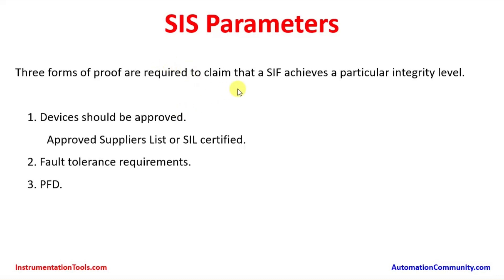Three forms of proof are required to claim that a SIF achieves a particular integrity level. First, devices should be approved — from an approved suppliers list or SIL-certified. Instruments and valves used in the safety instrumented system must come from approved suppliers and manufacturers, certified by agencies such as EXIDA or TÜV, which certify sensors, logic solvers, and final control elements against standards such as IEC. Second, fault tolerance requirements must be met. Third, the probability of failure on demand must be achieved.